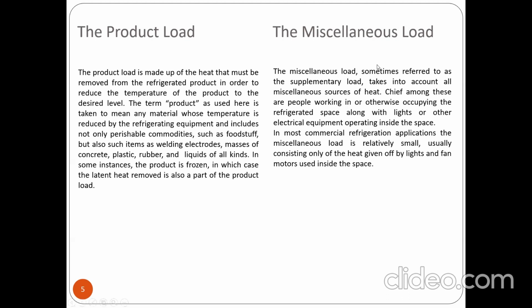Now, the miscellaneous load. Miscellaneous load, sometimes referred to as supplementary load, takes into account all miscellaneous sources of heat. Chief among these are people working in or otherwise occupying the refrigerated space, along with lights or other electrical equipment operating inside the space. In most commercial refrigeration applications, the miscellaneous load is relatively small, usually consisting only of the heat given off by lights and fan motors used in the space. Okay.